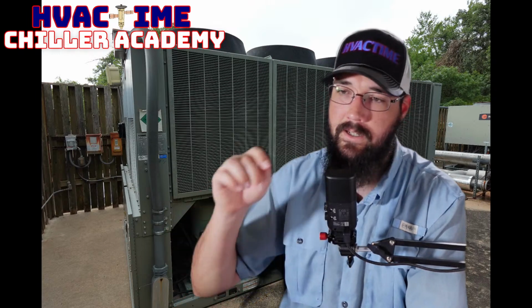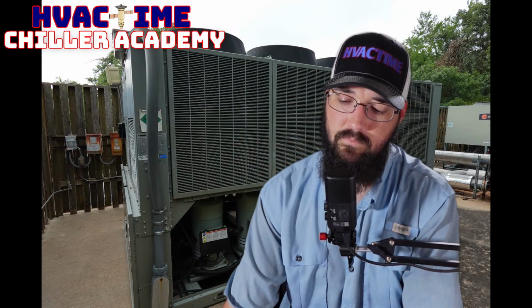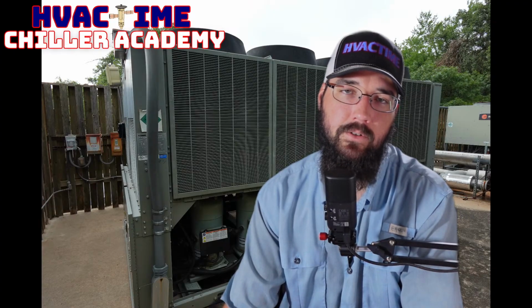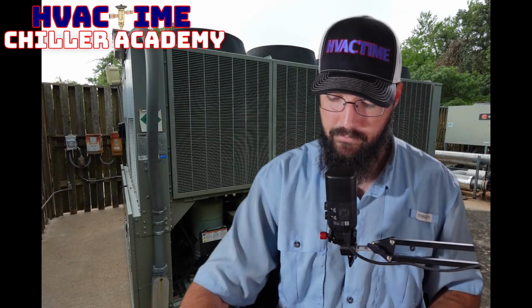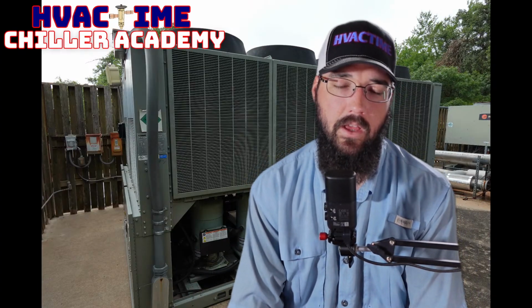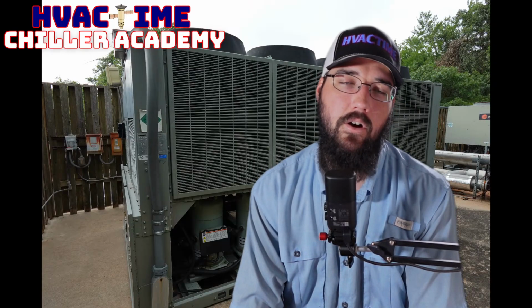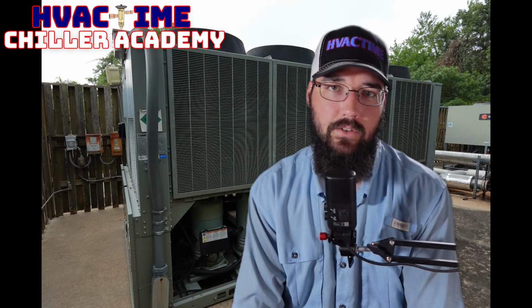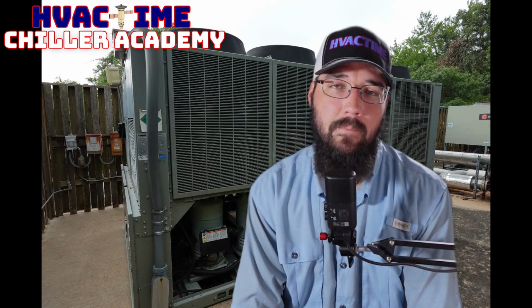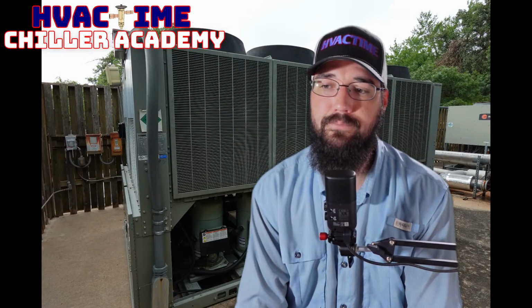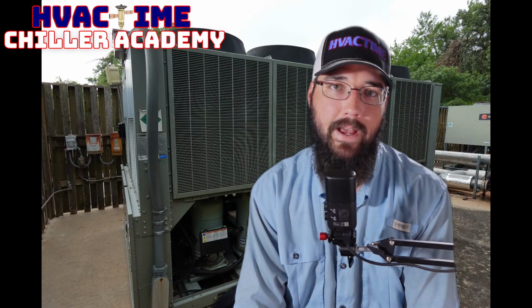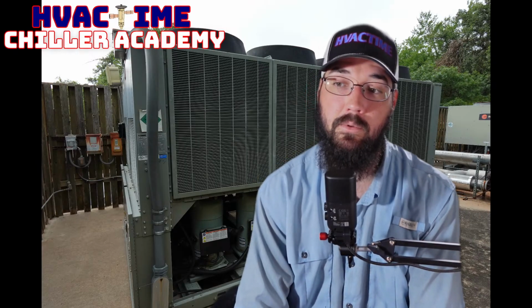Well, the issue with that, Tom, is it depends on the site. If they're running that short of a cycle, that would tell me that they're probably doing a processing run. So this is some kind of facility where they're doing batches of something, and they're trying to energy optimize, and they want to shut the chiller off in between batches instead of allowing it to maintain stable operation. They only need it to come on for 15 minutes at a time for that particular batch run, whatever they're trying to accomplish. That would be my assumption.